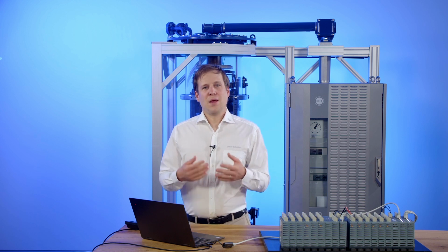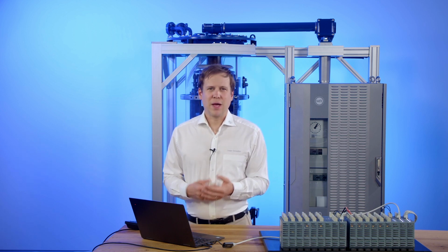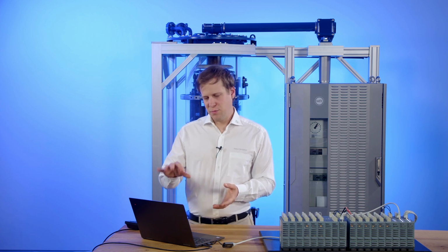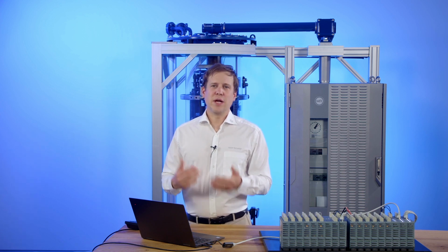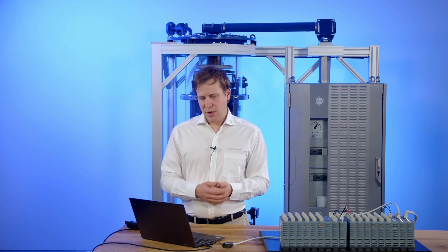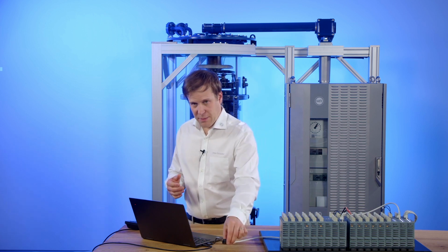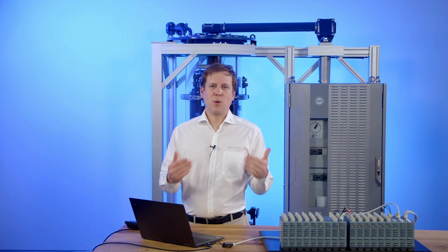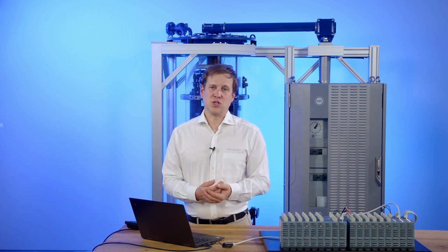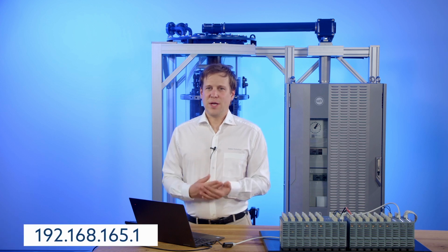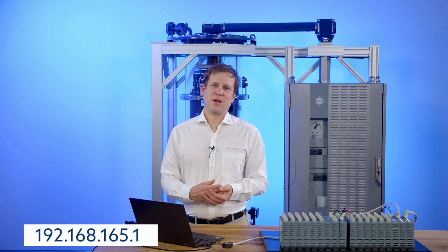Number 2, the ping.exe. I have added a little file into my desktop configuration. Whenever I connect to an ETOS system, I start the ping.exe to verify that the settings of my adapter and the settings of the ETOS system are perfectly matching, so I can open the visualization easily. Therefore, for sure you can by default configure an exe for your desktop, which will always ping the default IP address for ETOS, which is always 192.168.165.1.